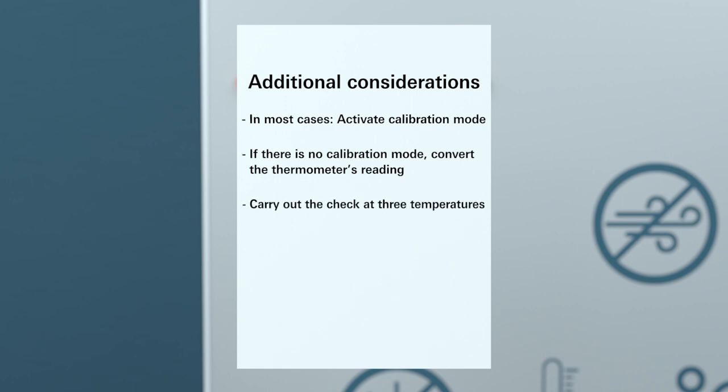The check must be carried out at three cavity radiator temperatures distributed more or less evenly over the temperature display range.